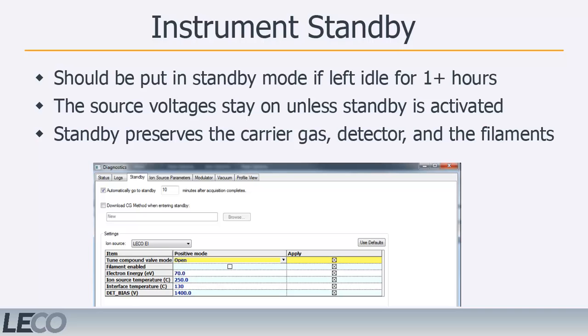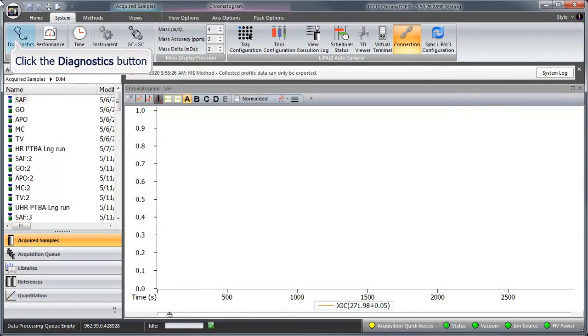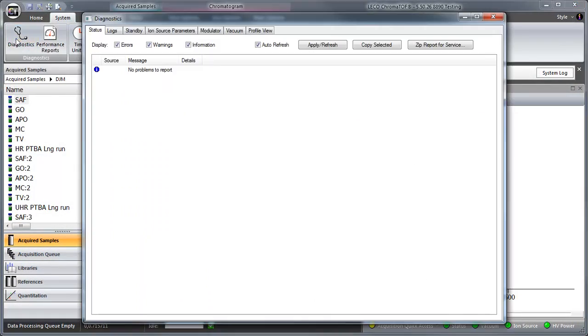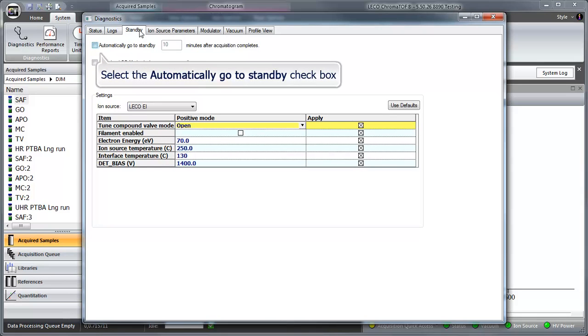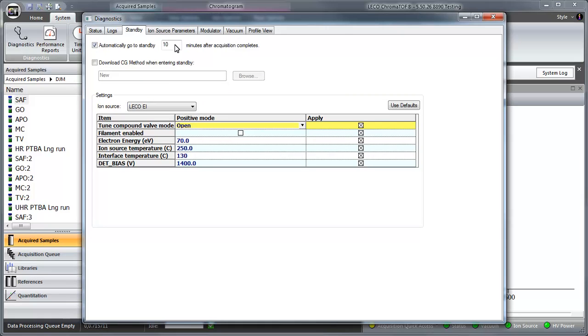The instrument should always be placed into a standby mode if left idle for more than 1 hour. By default, the filament voltage does not shut off after profiling, so enabling the ion source standby will greatly preserve the life of the detector and the filaments. To set up a standby procedure, go to the Diagnostics window and select Standby. Check the Automatically Go to Standby box and enter the desired time frame.